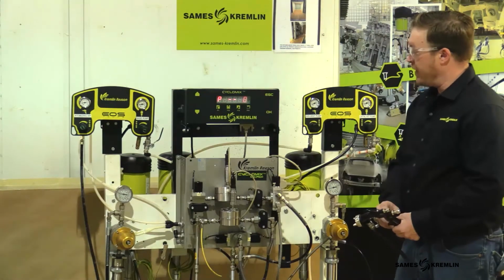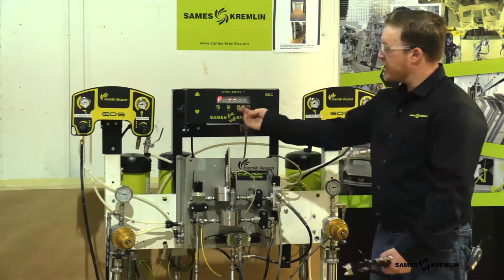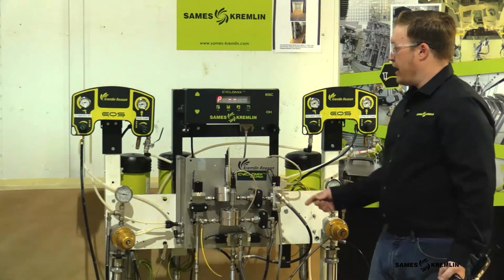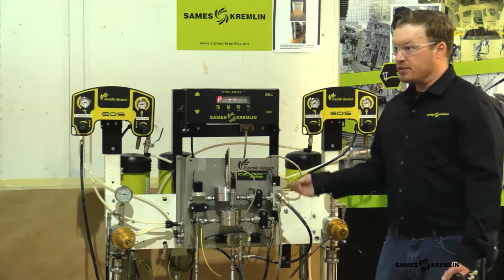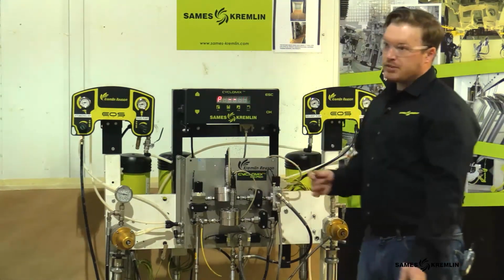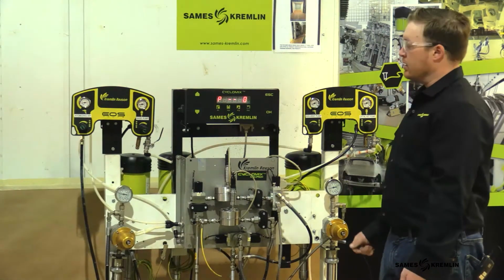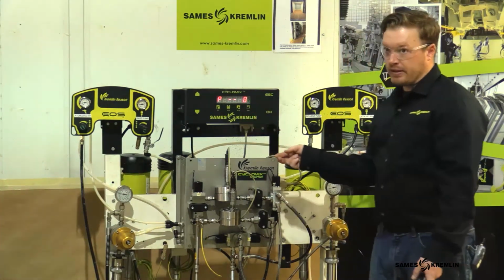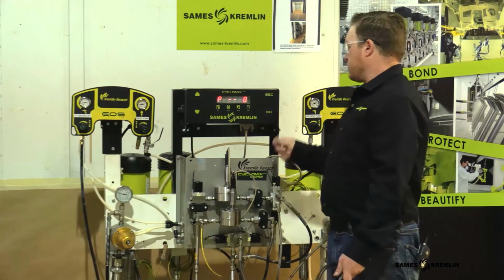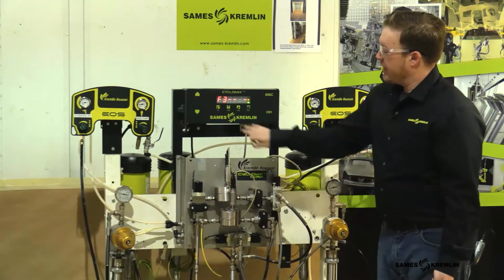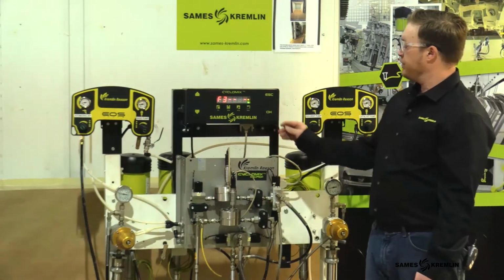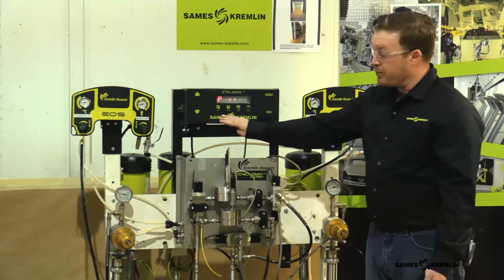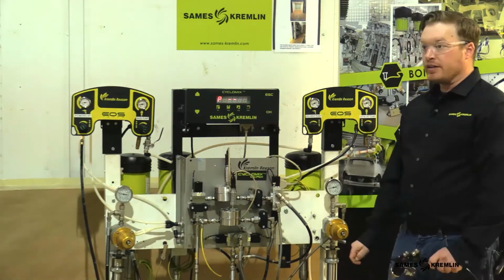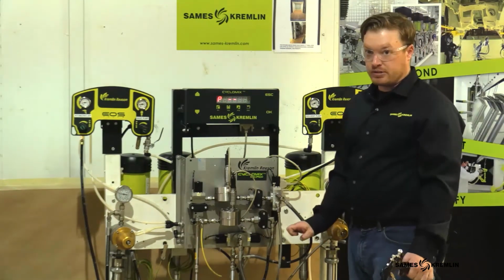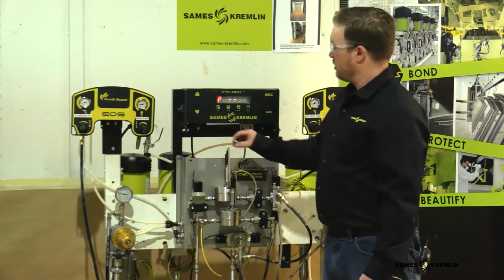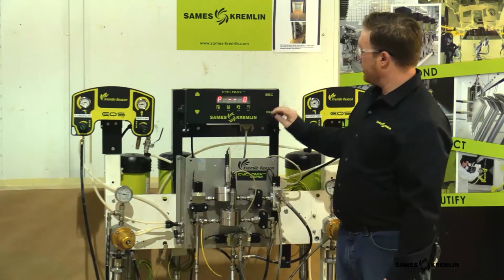The other thing that we have available now with some of the newer software is password protect. And with how easy it is to access this parameter screen, sometimes even by mistake, the screen is accessed. We've developed a password to prevent that from happening. And so what we'll see is I'm going to escape, and I'm going to re-enter my F3 parameter screen. And because we went right to P1, I automatically know that there is not a password put in place for this particular controller. So we'll scroll down, and it's very simple.